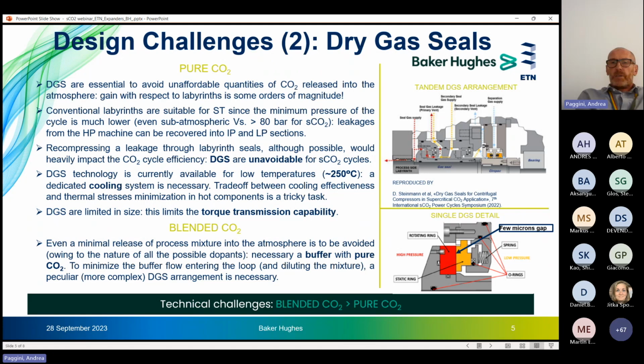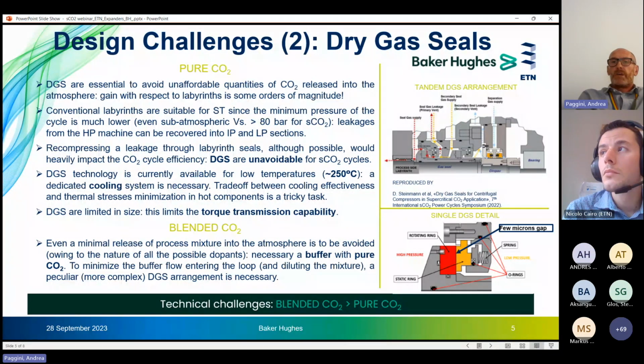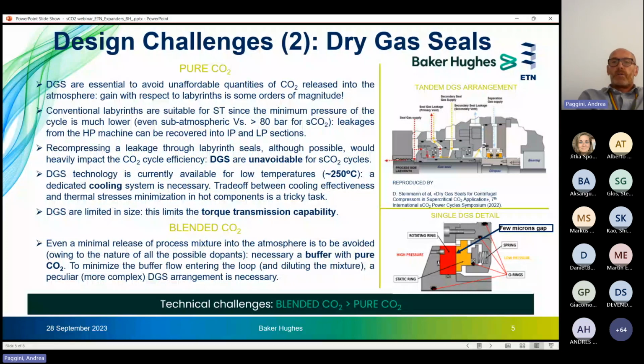One more point I wish to talk about, even if it has been touched on in the other presentation, is dry gas seals. Drag seals are unavoidable for sCO2 expanders. The reason is that with the minimum pressure of the cycle, which is typically above 80 bar, you cannot have a labyrinth design for the shaft end seals of the machine. It would result in a completely unaffordable leakage. And when I say unaffordable, it could mean a huge leakage to the atmosphere, or, in case the leakage is recompressed, which is a viable option, a huge recompression work, very much penalizing and detrimental to the cycle efficiency. So dry gas seals are mandatory for sCO2 expanders.